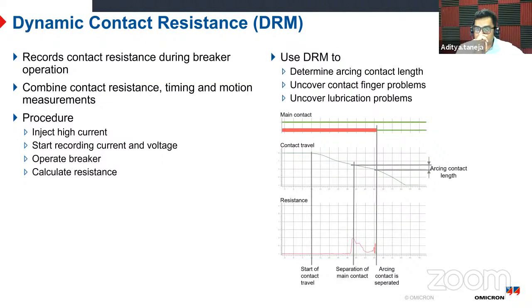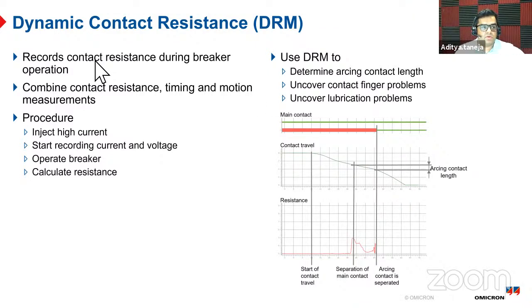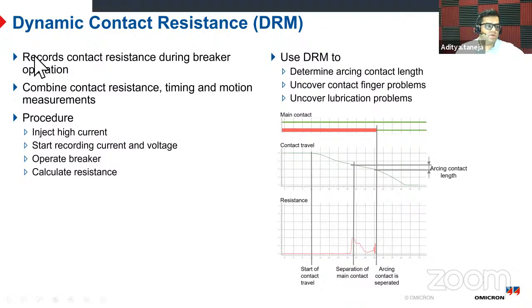Arcing contacts are something quite typical, and they deteriorate quite fast. So we look at contact resistance. In dynamic contact resistance, we measure the resistance while we operate the breaker. We keep injecting current and measuring voltage and simultaneously operate the breaker, so that we see the resistance profile over time, and that shows us the arcing contacts also. If there is any problem coming there, you will see it, and trust me, this is like opening a Pandora's box, because you don't see them normally in all the other tests, but when you see them, they tend to surprise you.